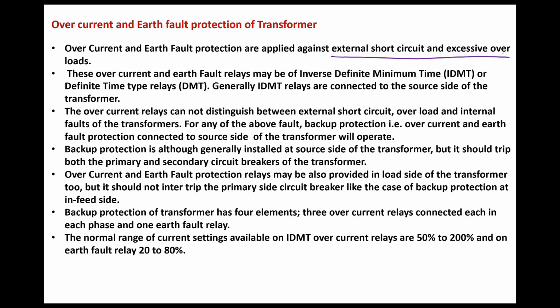For detection of these kinds of faults, which kind of relays will we use? We will use inverse definite minimum time (IDMT) relays. Generally IDMT relays are connected on the source side of the transformer. Overcurrent and earth fault protection is provided for the faults that occur outside the transformer, and for detection of these faults we use IDMT relays on the source side.